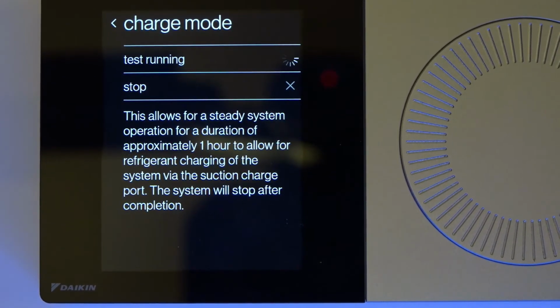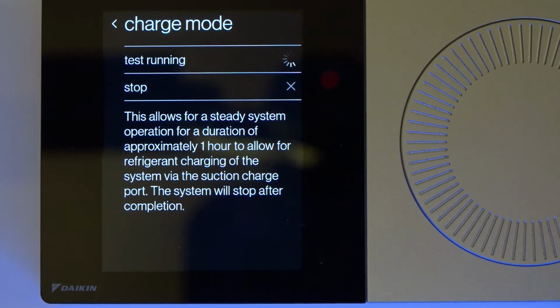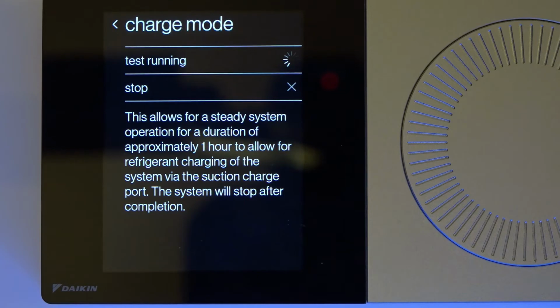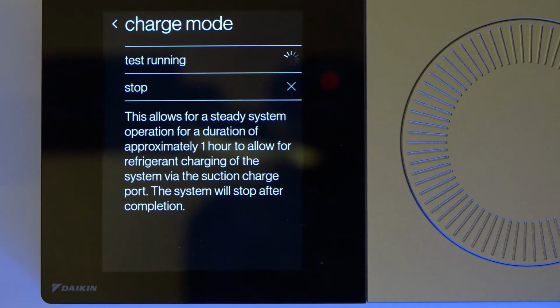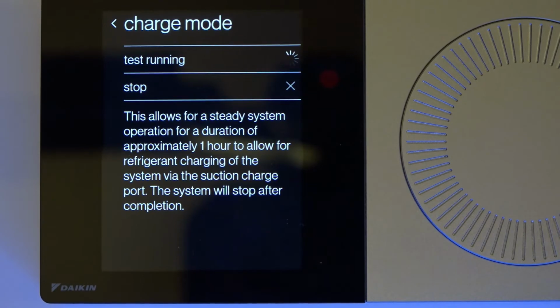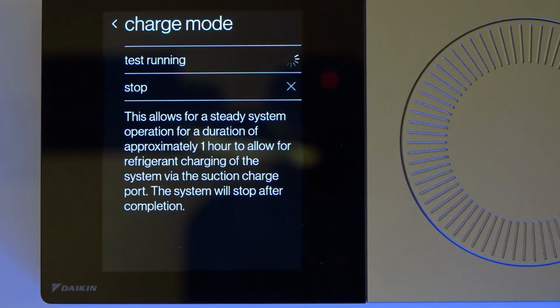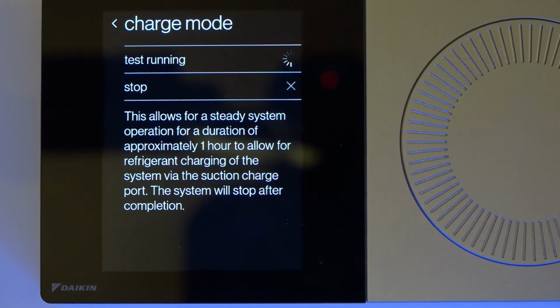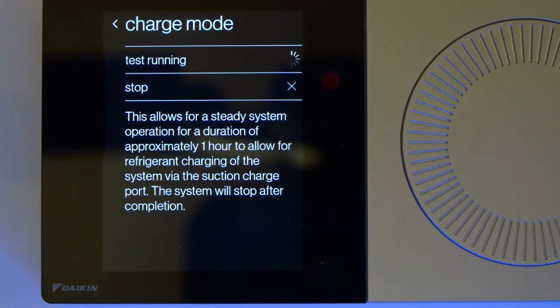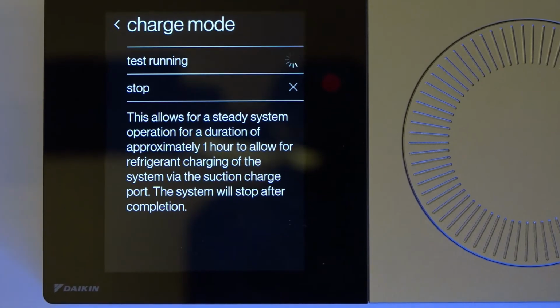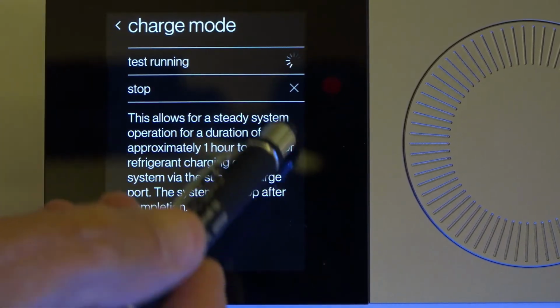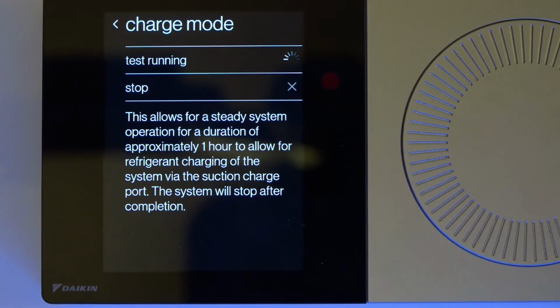This compressor never ever starts up loaded. It's always unloaded. The 20 SEER pulls about 3.42 amps to start the compressor. The 18 SEER is slightly lower, and then the Daikin Fit system or the Amana side discharge is going to be roughly in the 3 amp range as well. So this system pulls no amps to start the compressor, no light flicker inside the house when the unit's starting up. Now, you see the little spinning dial here. That tells me the test is running.